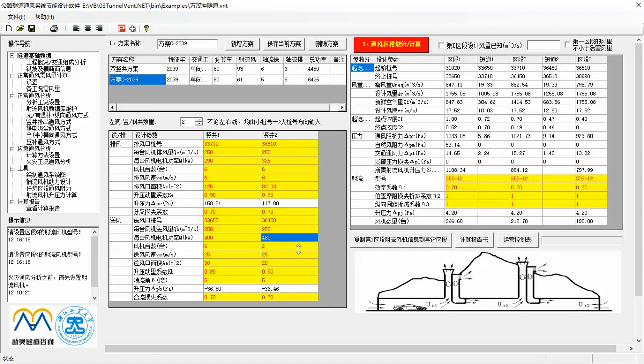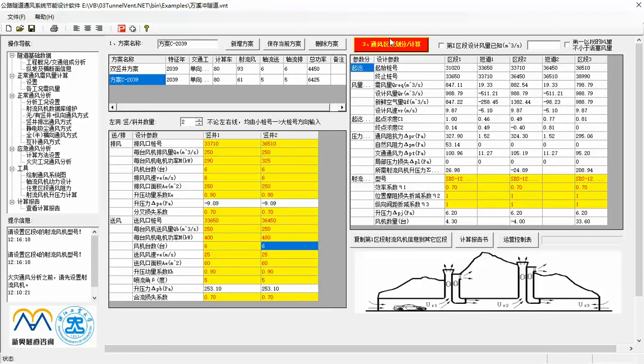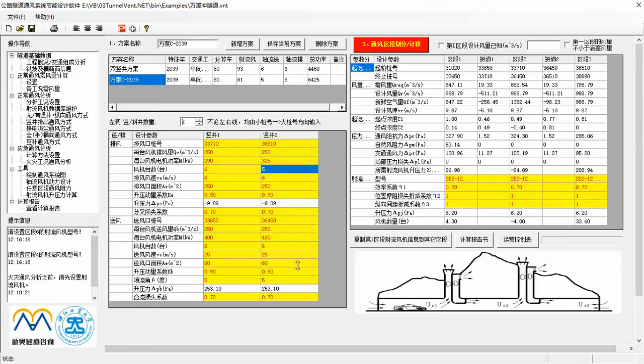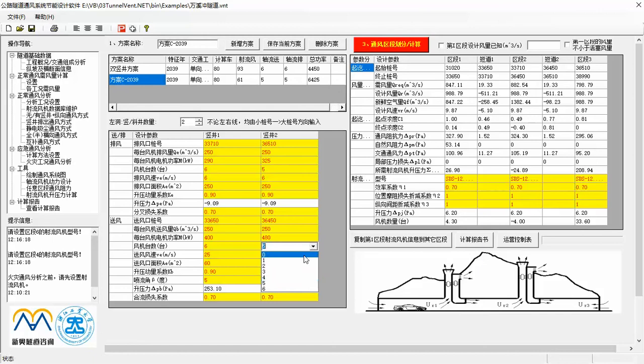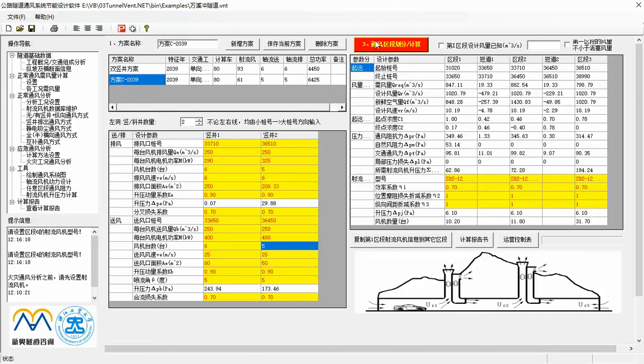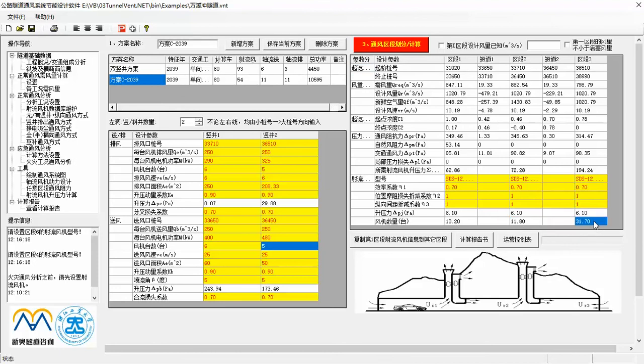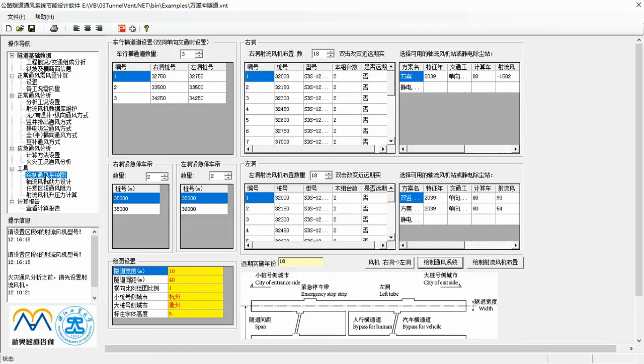And you can see the calculation results for each section in the right table, including starting and ending mileage, air demand, design and actual air volume, fresh air volume, concentration values and other results related to pressure balance. Finally, and most importantly, you can see the jet fan number that is needed to balance each ventilation section. Because of time limitation, I will continue to introduce other cases that use other ventilation modes and emergency ventilation analysis in next videos. Let us jump to the ventilation system diagram drawing function.